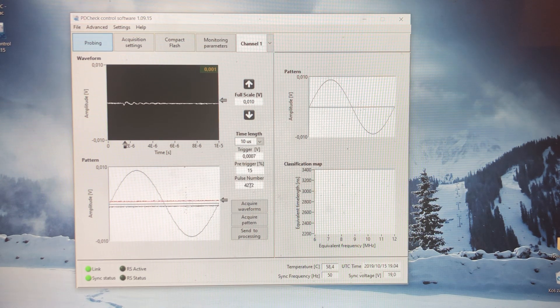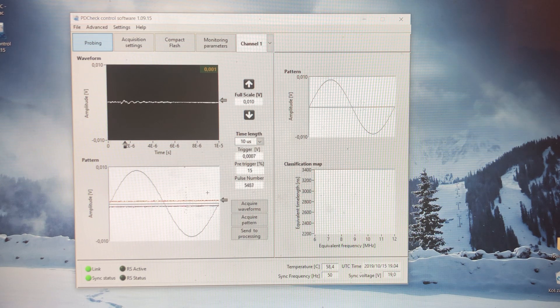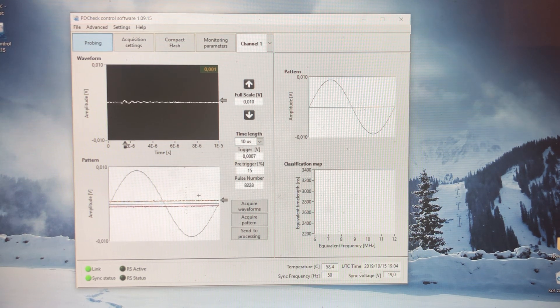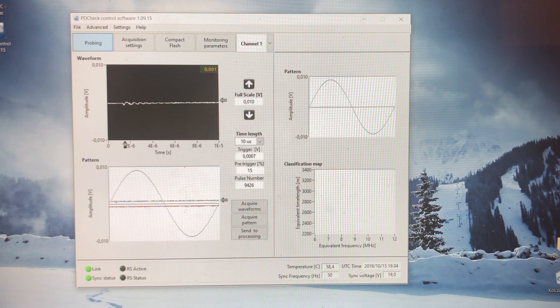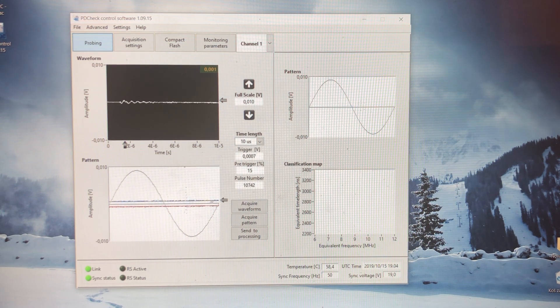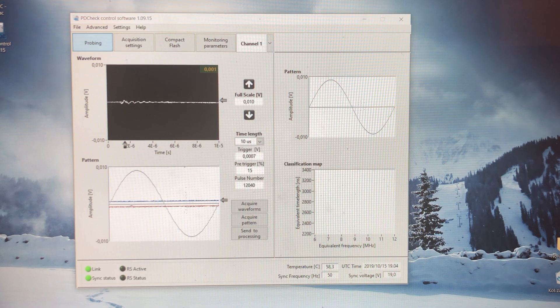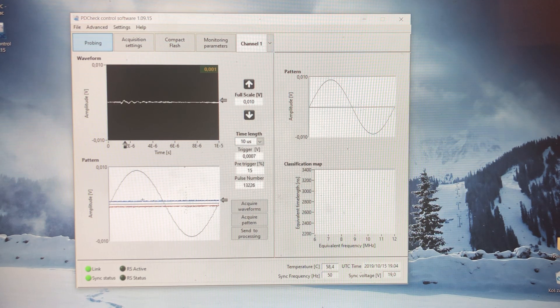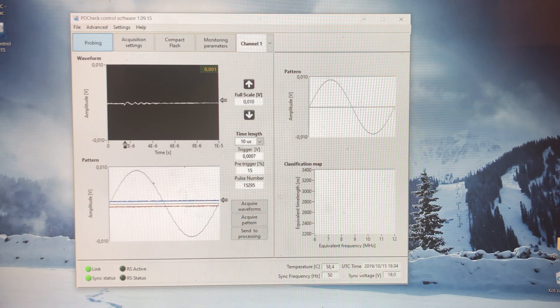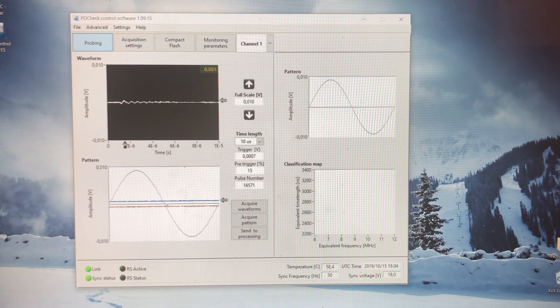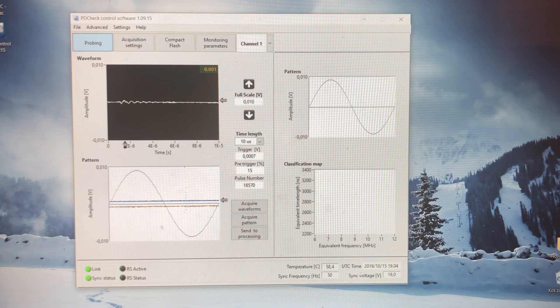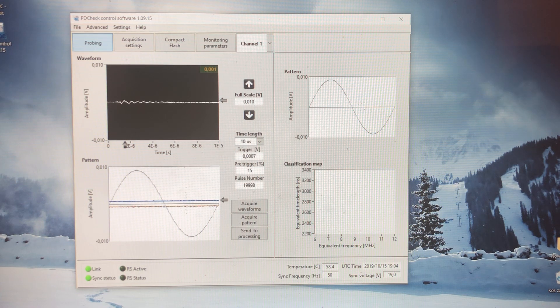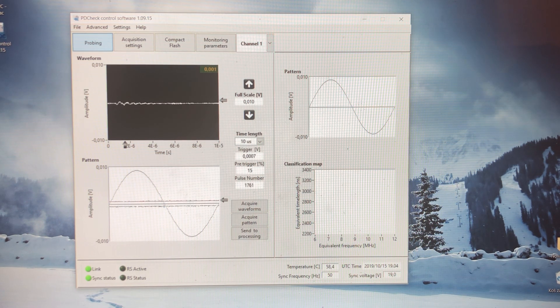How do I know it's noise? First of all, I pressed the button for high frequency noise on the PD simulator, but also I see that the dots are always the same, regardless of whether the sine wave is at minimum, maximum, or crossing the zero.